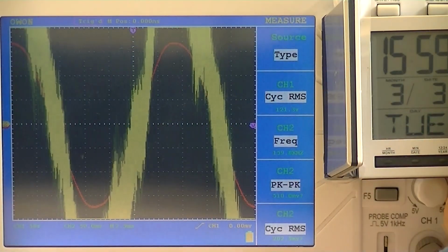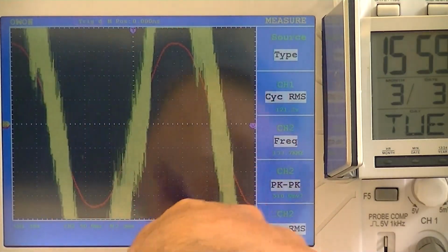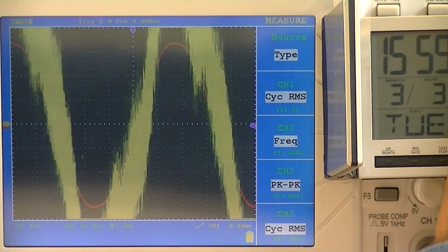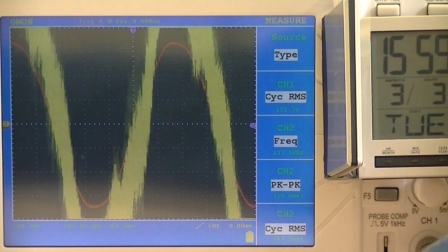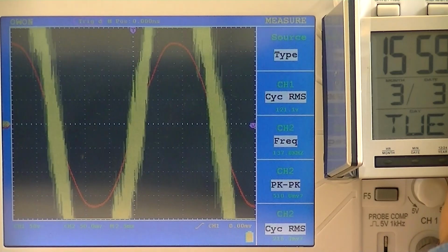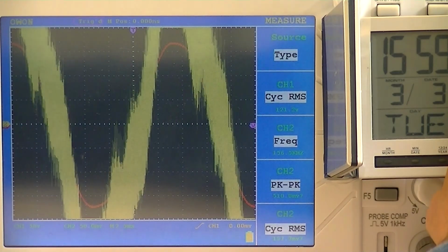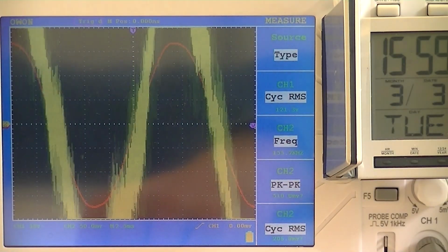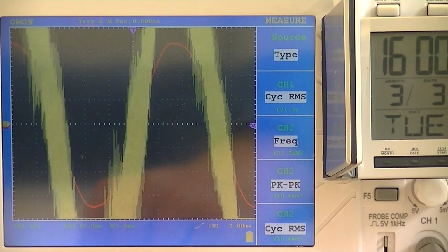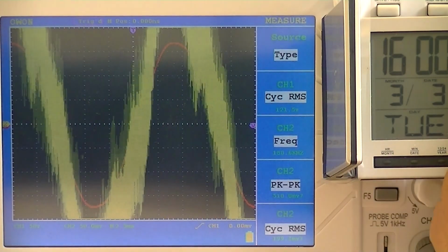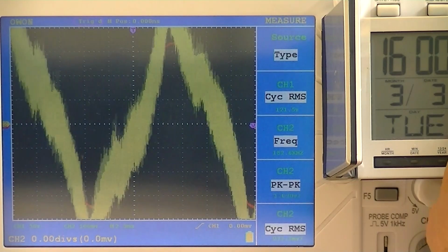I'm going to have to change the scale. You can see that that grounding waveform is shot right up. And we now have the AC sine wave. And I'm going to change the scale so we can see that grounding system. So the grounding system now is saying it's 200 millivolts RMS, 510. I'm going to have to change the scales to get an accurate measurement.